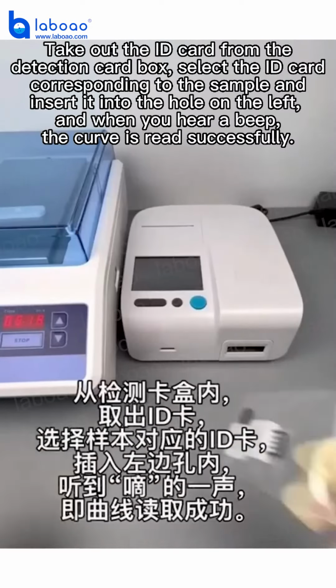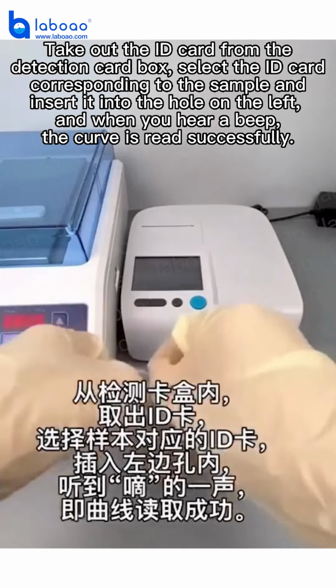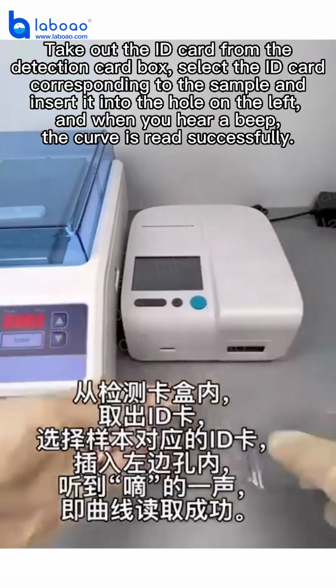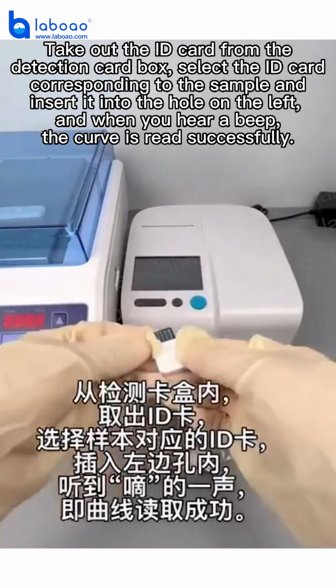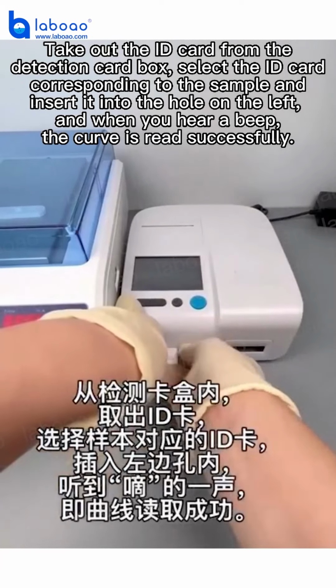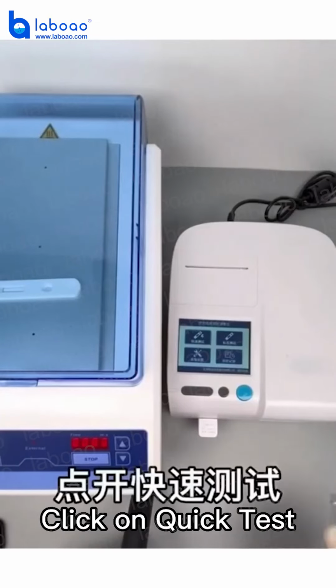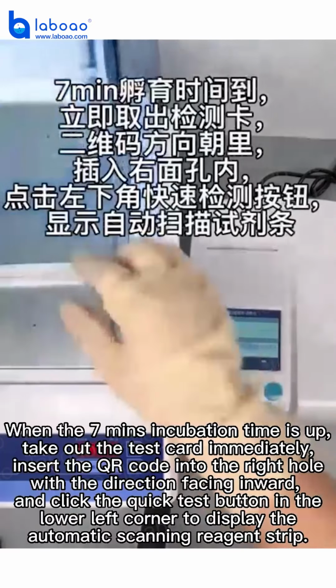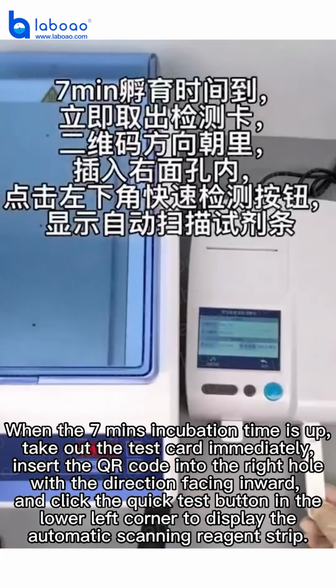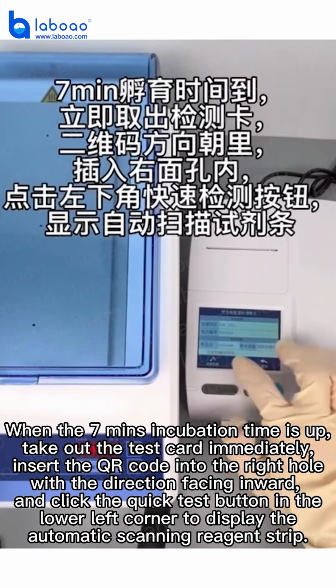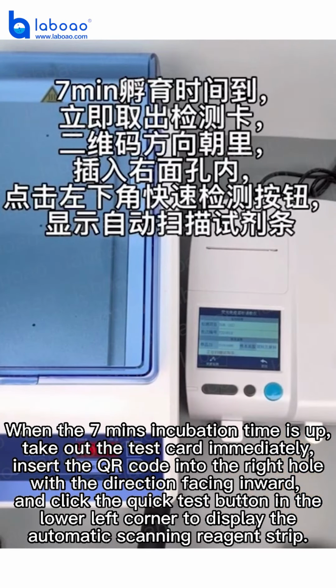Take out the ID card from the detection card box. Select the ID card corresponding to the sample and insert it into the hole on the left, and when you hear a beep, the curve is read successfully. Click on Quick Test. When the 7 minutes incubation time is up, take out the test card immediately. Insert it into the right hole with the direction facing inward and click the Quick Test button in the lower left corner to display the automatic scanning of the reagent strip.